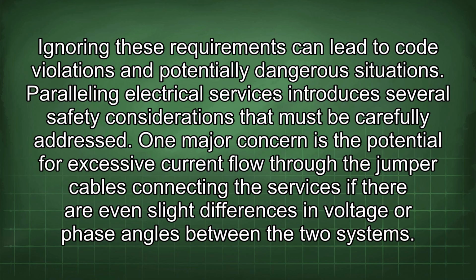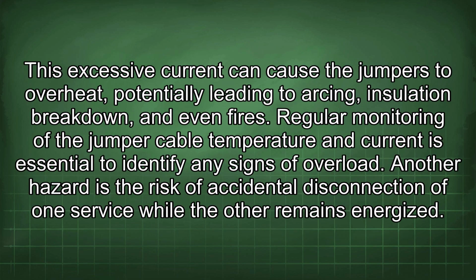Paralleling electrical services introduces several safety considerations that must be carefully addressed. One major concern is the potential for excessive current flow through the jumper cables connecting the services if there are even slight differences in voltage or phase angles between the two systems. This excessive current can cause the jumpers to overheat, potentially leading to arcing, insulation breakdown, and even fires. Regular monitoring of the jumper cable temperature and current is essential to identify any signs of overload.